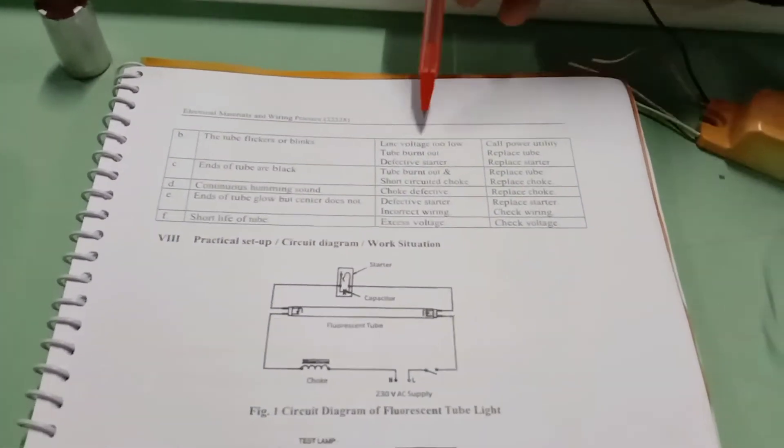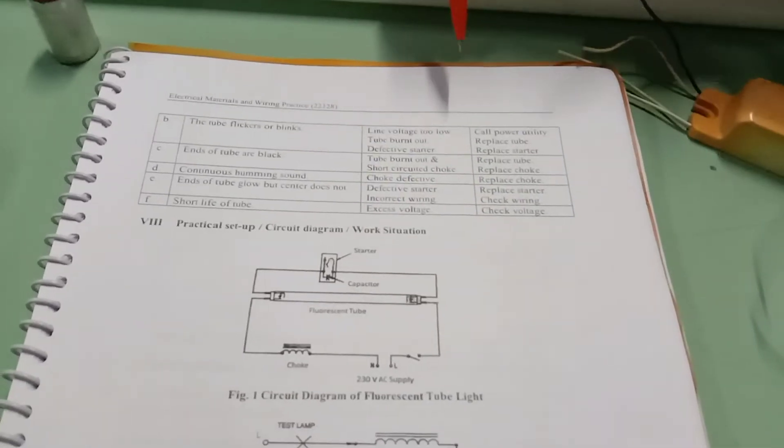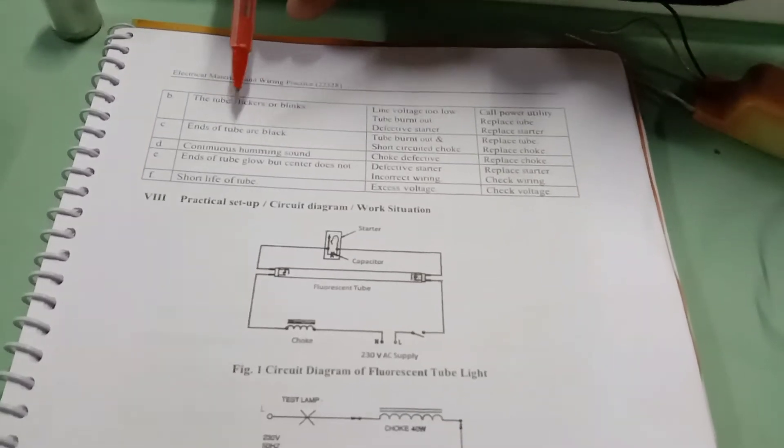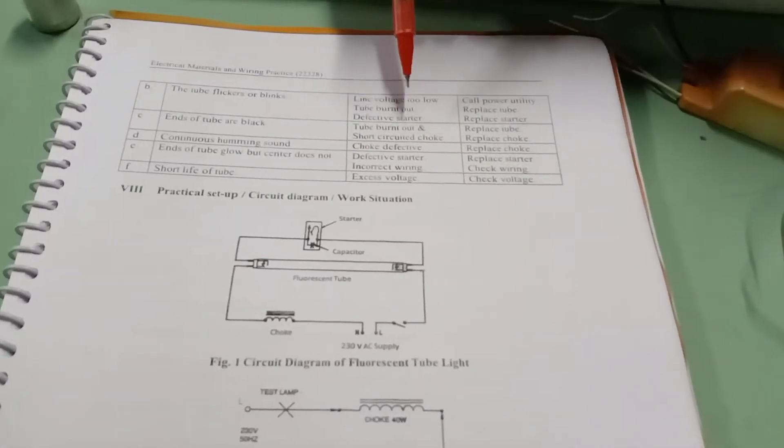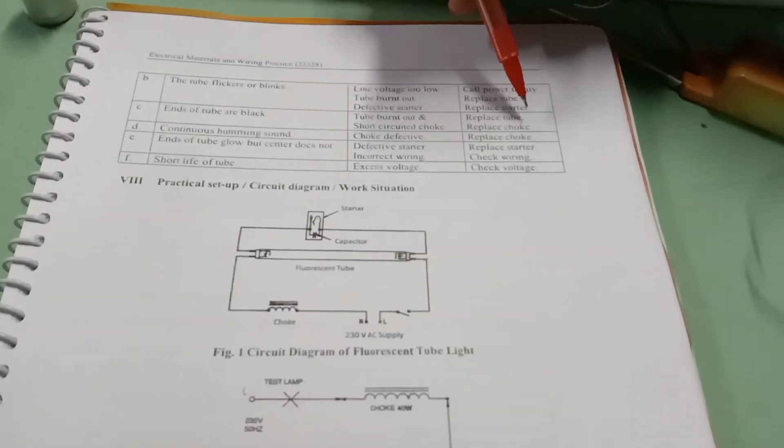If the tube light flickers or blinks it means the line voltage is too low. These are the different remedies and we have to work on it. If the end of tubes are black means tube burnout and short circuited choke. We have to replace that choke.